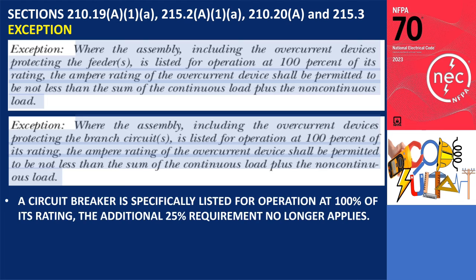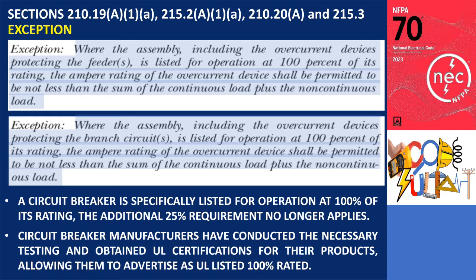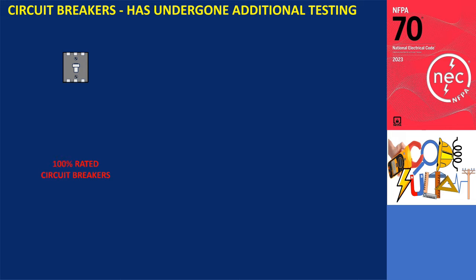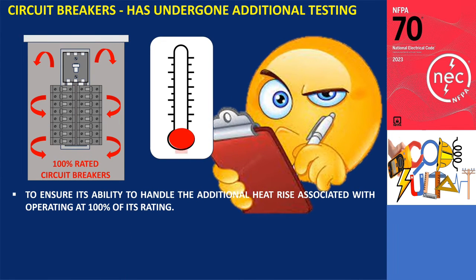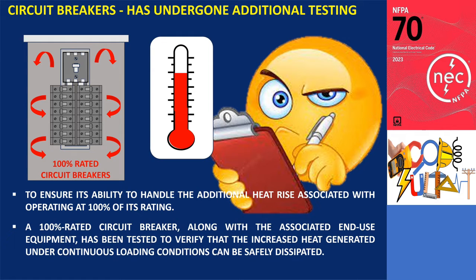This exception means that when a circuit breaker is specifically listed for operation at 100% of its rating, the additional 25% requirement no longer applies. Instead, the device simply needs to handle the total of the continuous load and the non-continuous load. Many circuit breaker manufacturers have conducted necessary testing and obtained UL certifications, allowing them to advertise as UL listed 100% rated. This signifies that the equipment has undergone additional testing to ensure its ability to handle the additional heat rise associated with operating at 100% of its rating.